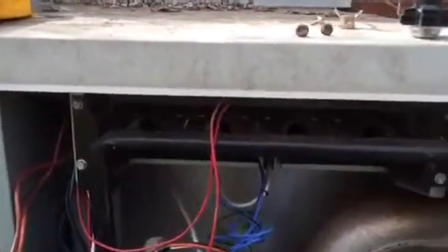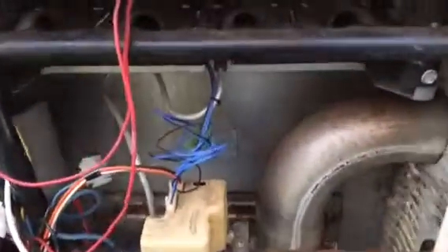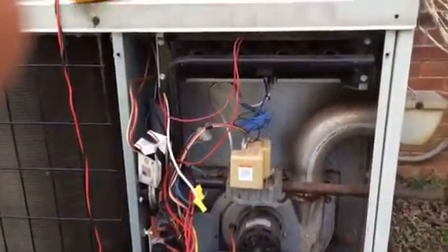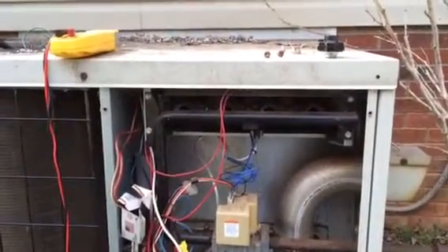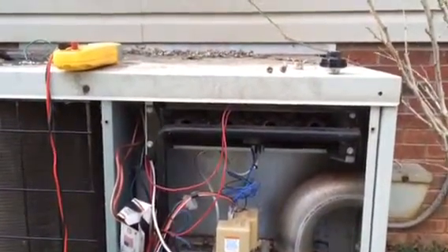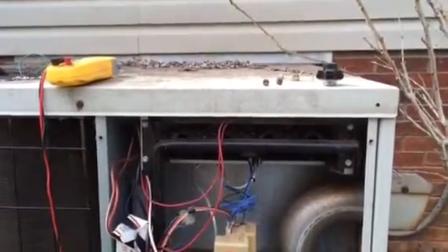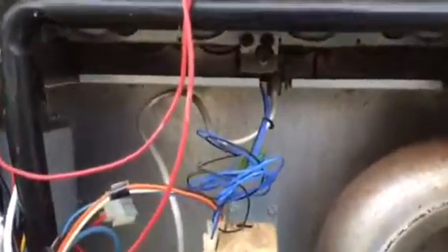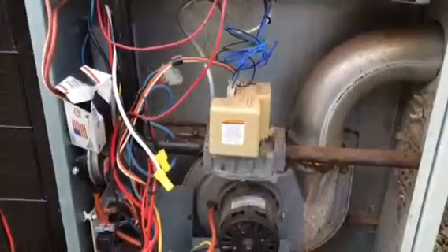Scott here with the day in the life of a heating and air conditioning tech. I went ahead and put my wires back onto the original rollout switch. And I forgot to mention the other reasons that a rollout switch could open up. One being the orifices are not getting sufficient gas in from the burners. The orifices are on the other side of this burner assembly, and that's what shoots the natural gas through there, and then it comes in contact with the spark ignition or hot surface igniter assembly for the smart valve.